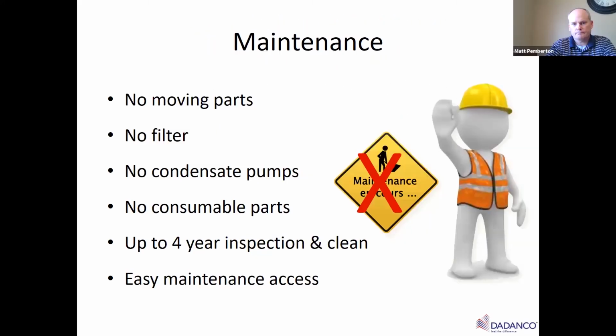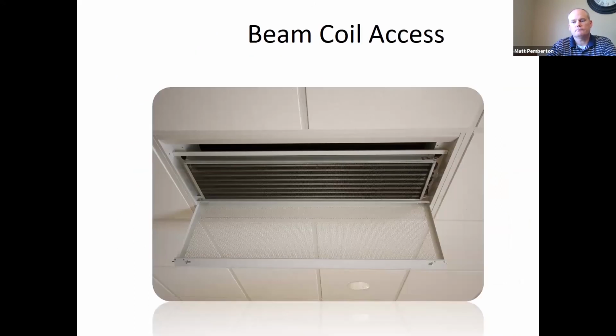And lastly, they do provide on the perf panels themselves a fold-down area where you can go in and actually change that out. This was a big issue to some users with chilled beams. And they've found out after having these installed for 5 to 10 years, there might be 1 or 2 cycles within that time that they actually have to go in and sweep those out. So it's not a very dusty environment, and it certainly works against the convective ideas that we have set up.